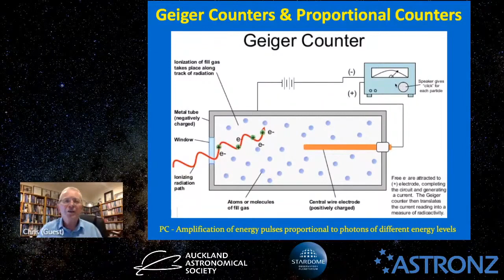It counts the photons. There's a problem with that, of course: it's not easy to differentiate between them. If you're allowing a wide range of X-ray photon energies in there, it won't tell you how many are at particular energy levels. So they came up with another development, proportional counters, whereby they could amplify the energy pulses from this process of ionization, and the amplification was proportional to the photons of different energy levels. So if you had more photons of one energy level than another, and both were coming through your filter, your instruments would tell you that in proportion you've got more at the higher levels. So that's how they measure X-ray photons.